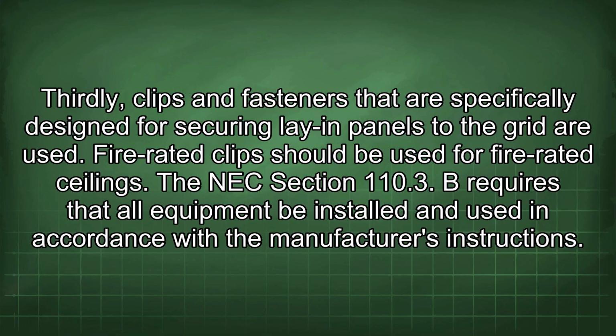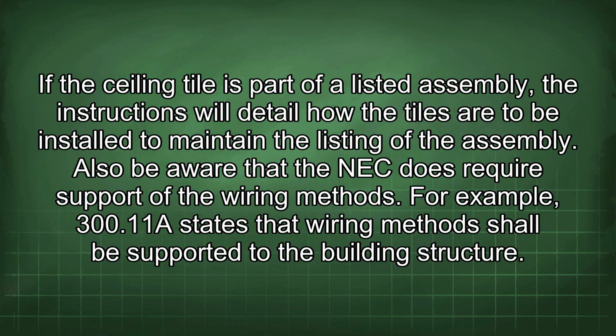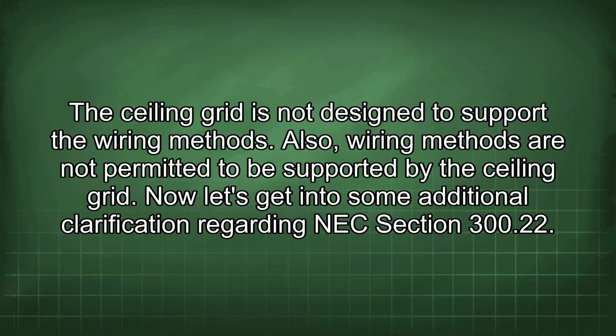The NEC Section 110.3(B) requires that all equipment be installed and used in accordance with the manufacturer's instructions. If the ceiling tile is part of a listed assembly, the instructions will detail how the tiles are to be installed to maintain the listing of the assembly. Also be aware that the NEC does require support of the wiring methods. For example, 300.11 states that wiring methods shall be supported to the building structure. The ceiling grid is not designed to support the wiring methods. Also, wiring methods are not permitted to be supported by the ceiling grid.